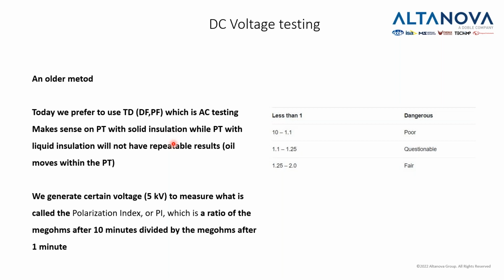which is the ratio of megaohms after 10 minutes divided by megaohms after 1 minute. And if that number is, as you can see here, less than 1, then we have a dangerously bad insulation. If it's between 1 and 1.1, it is poor. If it's between 1.1 and 1.25, questionable, and between 1.25 and 2, it is fair.